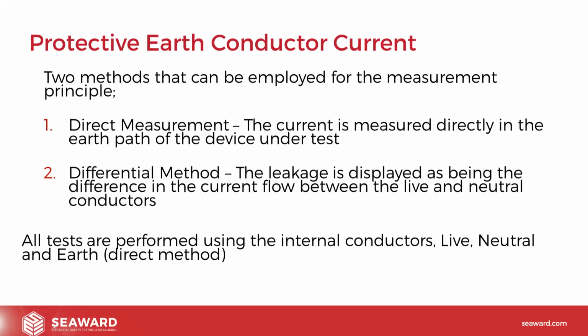As the name suggests, the differential method measures the differences in the current flowing in both the live and neutral conductors. So in this case, it does it slightly differently. It measures the current flowing up through the live conductor and measures the current flowing back via the neutral conductor. Now, in an ideal world where there's no leakage existing, the current flow would be zero, and therefore what we would have is a balanced supply, i.e.